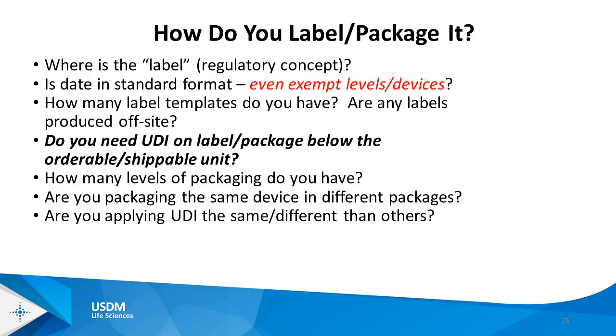And again, on standardized date format, understand that this is an additional requirement that happens to also be in the UDI rule. It goes on all device labels, all levels, regardless of whether you're subject to UDI or any particular packaging level is subject to UDI. Everything needs to be in that standardized date format.